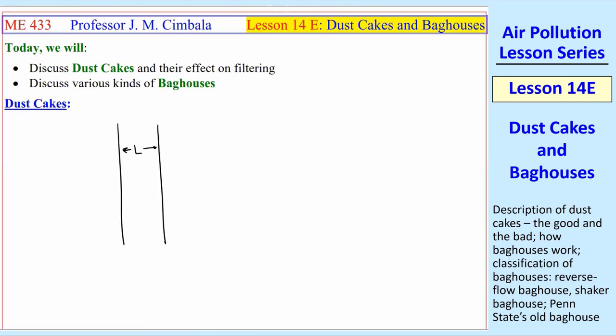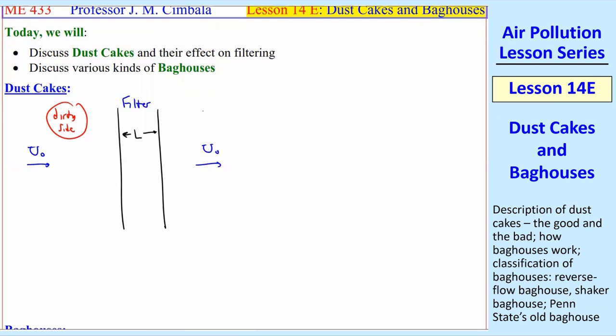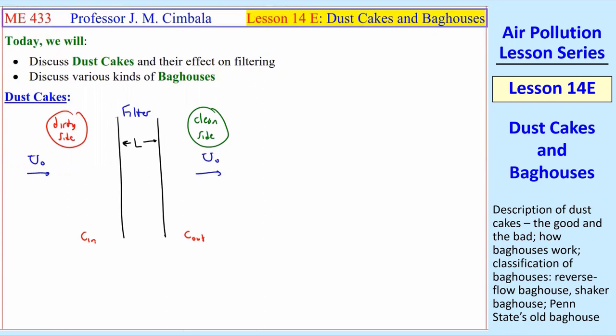So what is a dust cake? Consider some filter with airspeed before and after the filter. Upstream of the filter is called the dirty side, and downstream of the filter is called the clean side. You have some mass concentration coming in and some mass concentration coming out, as usual. But over time, you start to get dust collecting on the surface of the filter. A lot of the dust collects inside as well, but we're interested in what happens on the outside of the filter. This is called a dust cake — just a buildup of particles on that filter.